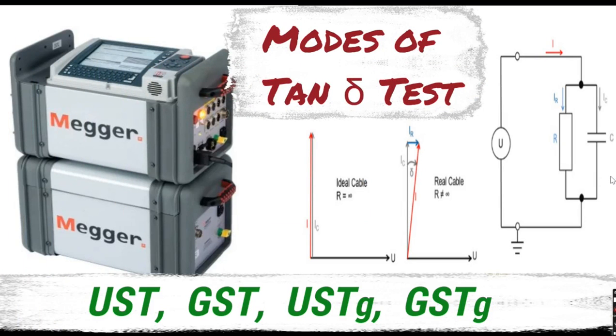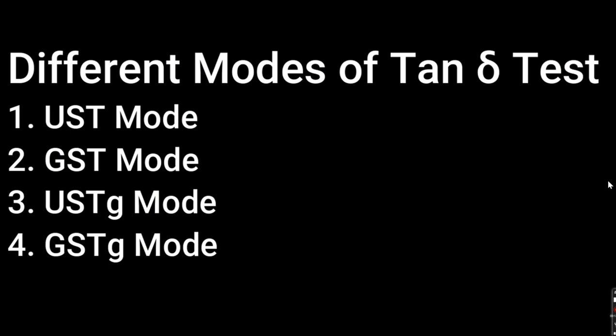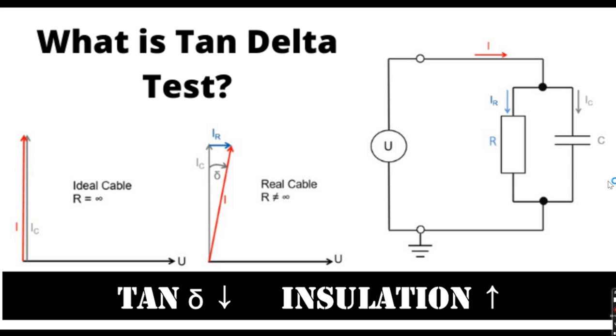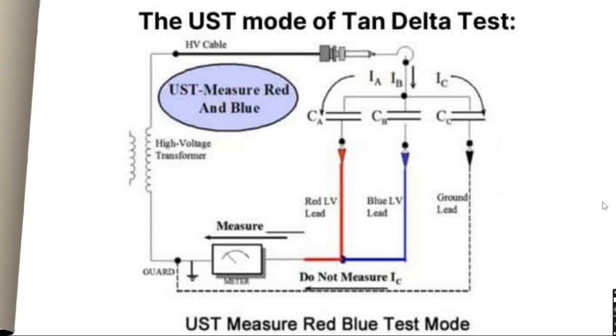Today we shall talk about different modes of tan delta testing for electrical substation maintenance. Tan delta testing for different equipment is a very common test performed, but to carry out the test correctly and get perfect results, it is important to know which mode should be used where. Tan delta test is also known as dissipation factor test or loss angle test. For a perfect insulator, the tan delta should be zero; however, since no perfect insulator exists, the tan delta is always more than zero. Simply put, the lesser the tan delta value, the better the insulation.